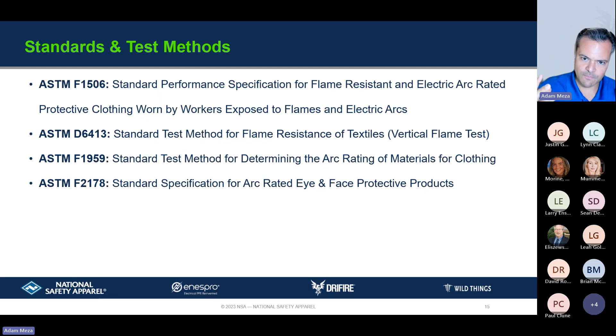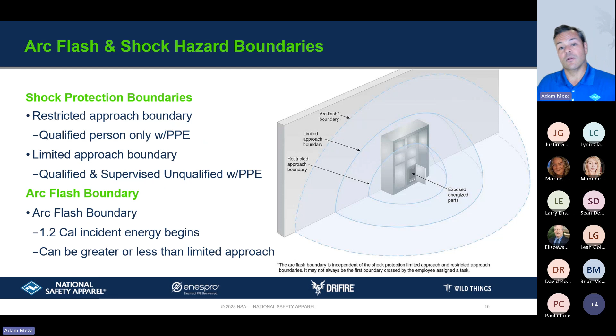Now, some of the boundaries I like to mention are the shock approach boundaries and the arc flash boundary. The restricted approach boundary is the inner bit where only qualified persons can go, with PPE. The limited approach boundary is for qualified and unqualified persons, with PPE. Then there's the arc flash boundary, which is different, where the 1.2 calories begin, meaning you have to start wearing arc flash gear at 1.2 calories. That changes depending on the calculation, so it can be inside or outside the shock approach boundaries.